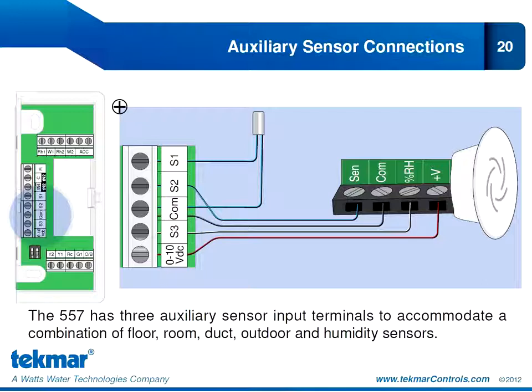If we only want to take into account the external humidity measurement, then we can easily disable the built-in humidity sensor on the 557. We've also shown here a slab sensor connected to one of the auxiliary sensor terminals, and that would be important if we're doing radiant floor heating or cooling and we want to control the floor minimum and maximum settings.